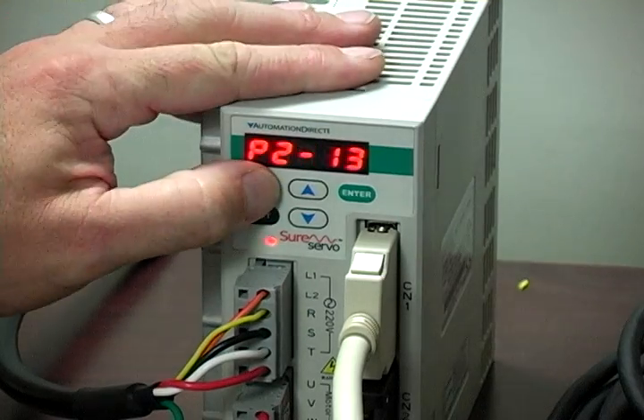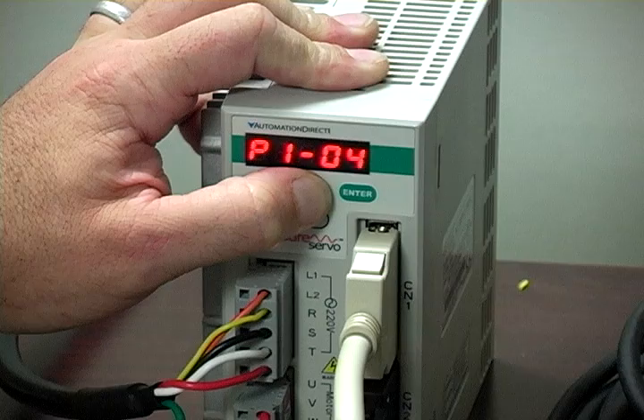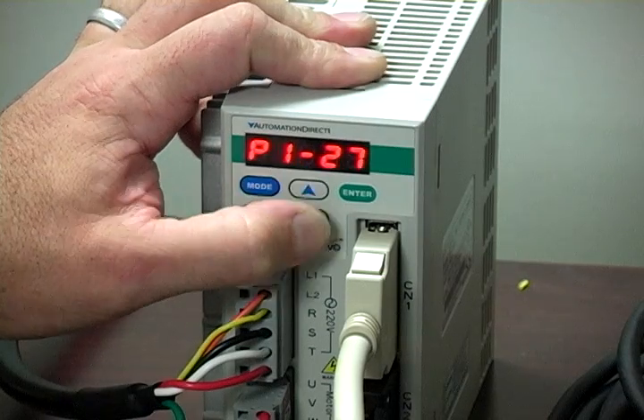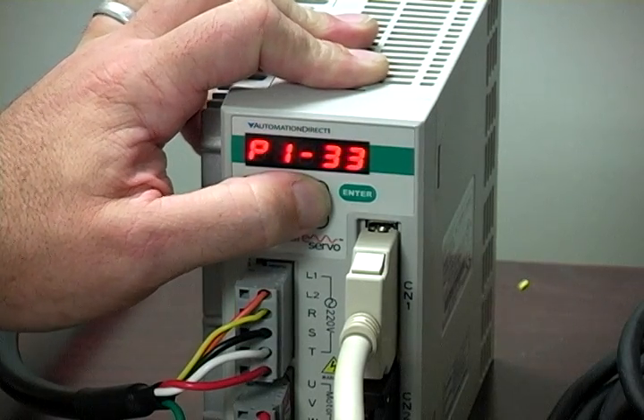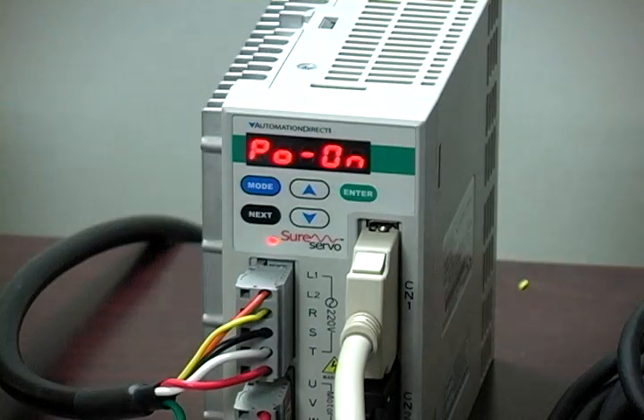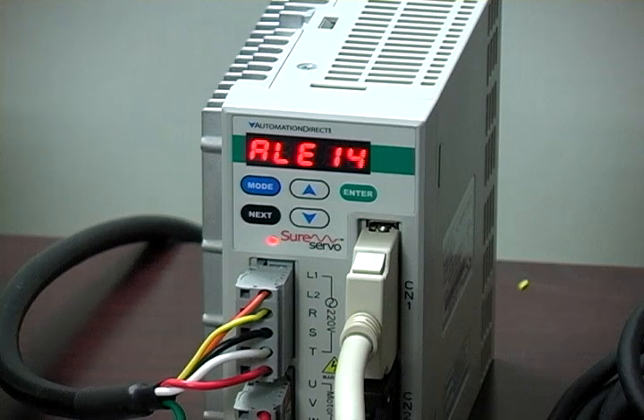Parameter P1-33 selects incremental or absolute position mode. Enter a value of 0 for absolute mode or enter 1 for incremental mode. We'll start with 1 for incremental or relative moves. Remember to cycle power to the drive after configuring the drive I.O. so that your changes will take effect.